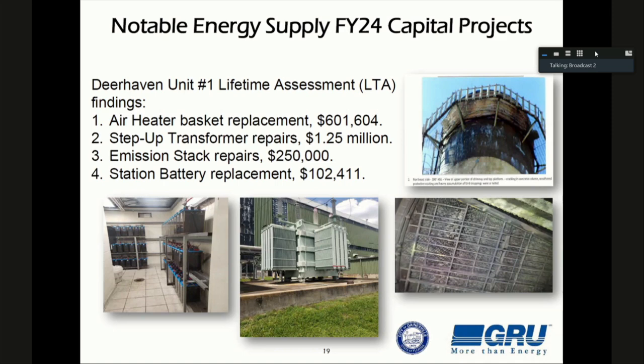If you look in the far right-hand corner, that shows you the inlet to the air heater baskets. You should be able to see through those baskets, but you can see the fouling that's in there, and you can see the warping of the plates. So we're not going to replace all the air heaters. We're going to replace what we need to get us reliably through 2027, and that's about $600,000 anticipated cost.